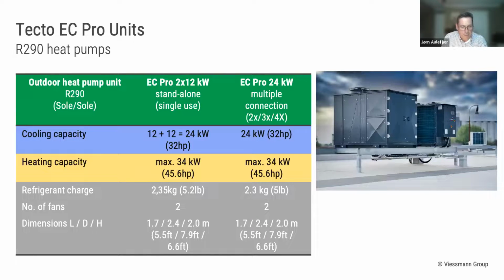Of interest to this audience, I'm quite sure, the refrigerant charge. So as you see, it's approximately 5 pounds per heat pump. That, of course, exceeds the indoor limitations here in the US. And it's going to be interesting to see what will be eventually the outdoor charging limit and how that's going to be applied. But of course, this is exceeding the current indoor limitation. So these heat pumps are made for outdoor placement. It's the same thing in Europe. It is exceeding the indoor charging limit. So all of them are outdoor placement only at this point.